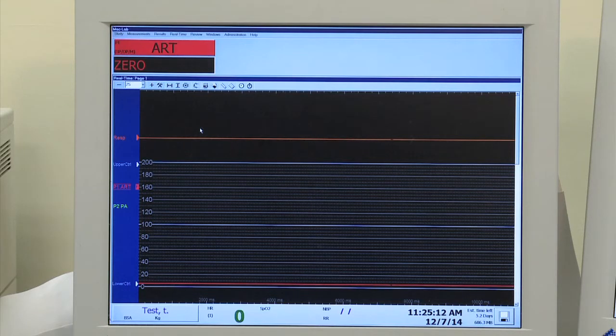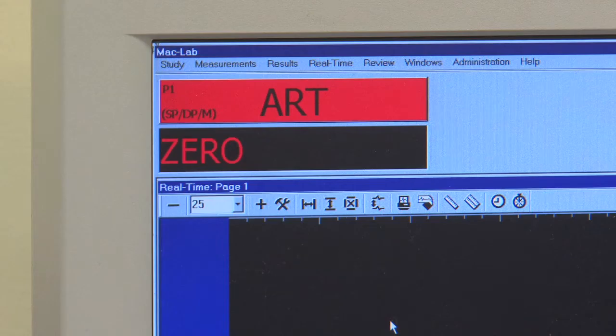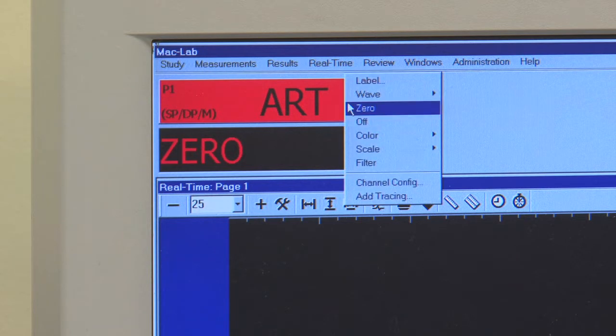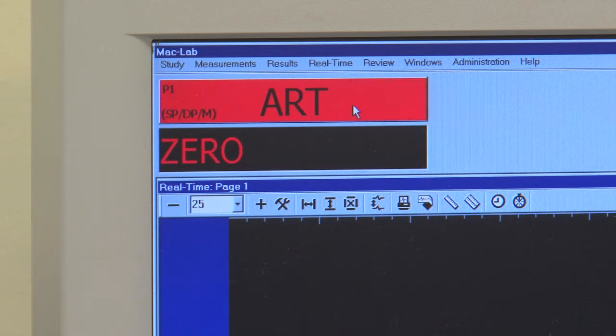The first step we need to do is 0 the RXi system to the Hemosystem, but we have to ensure that the channel 1, which carries the patient's aortic pressure, is at 0. If it says 0, this channel is not activated and will not provide us an accurate 0. What we need to do is ask the tech to 0 the system first. So we have to ensure that this channel is getting a 0 signal. We want to 0 it to an open transducer.